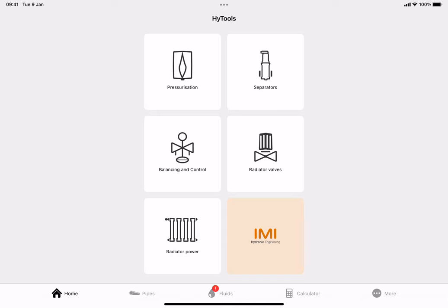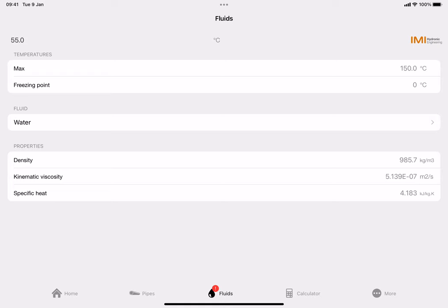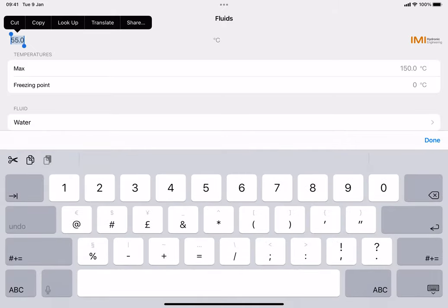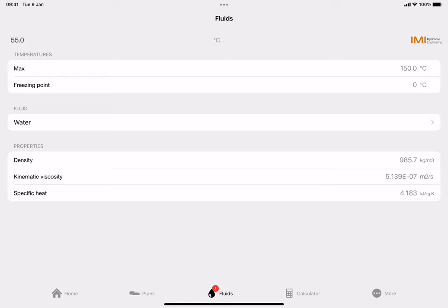The next thing that you want to do - and this is crucial to any design you're going to do - is the specific heat capacity of water, which is generally about 4.183 kilojoules per kilogram at 55 degrees flow temperature. At the bottom of the page click on 'fluids' and you can see on the top left I've highlighted 55 degrees. You can change that to whatever system you want to do, but because of new Part L regulations we're saying maximum flow temperatures of 55 degrees - this makes it much easier to get better calculations.